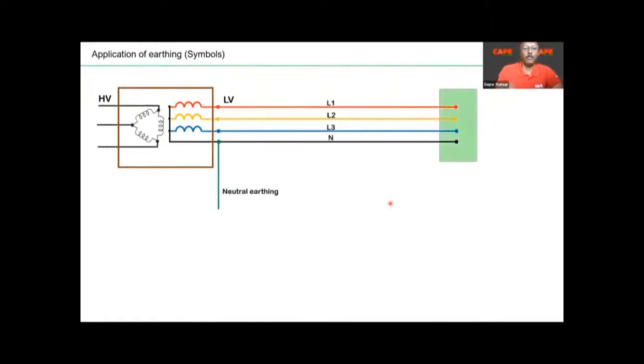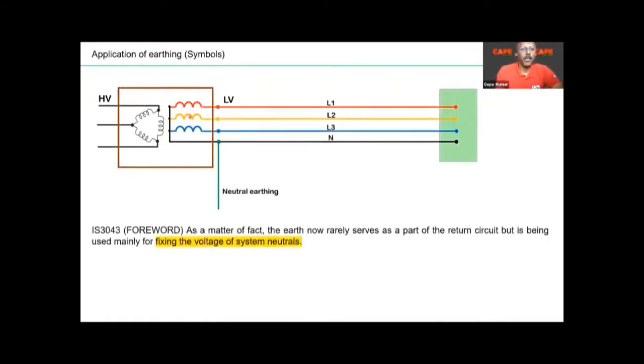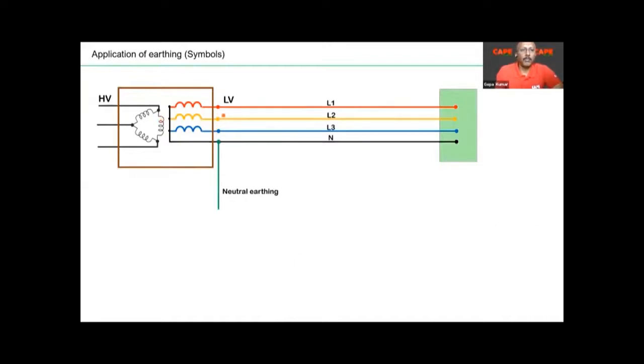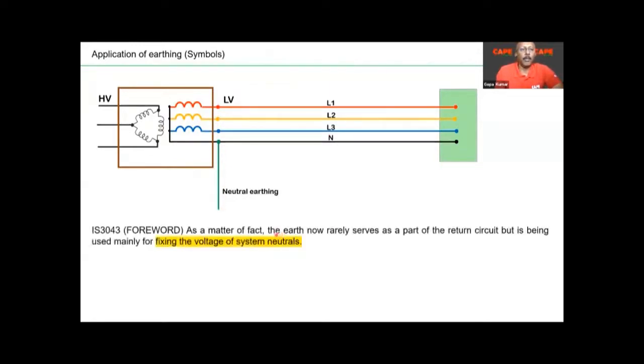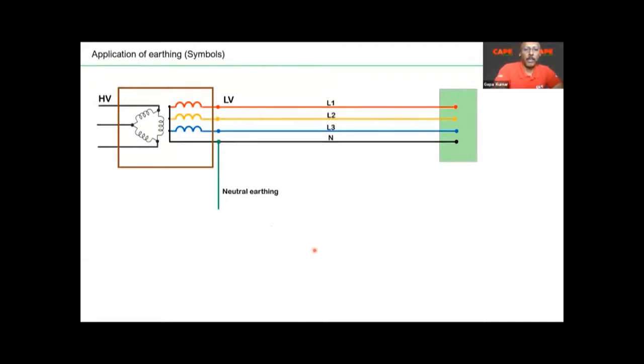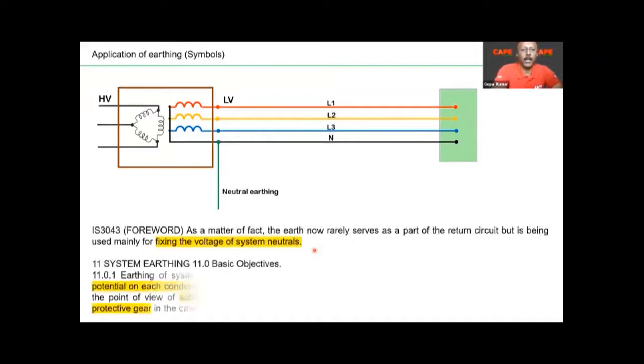Now imagine a transformer neutral. I'm just showing you a picture of a transformer. The three-phase goes to the equipment. You have the neutral, and the neutral is earthed. If you look at the foreword of IS 3043, what is written is, as a matter of fact, the earth now rarely serves as part of the return circuit, but is mainly used for fixing the voltage of system neutrals. So earthing is used for fixing the voltage of the neutral. That means it is a functional requirement.